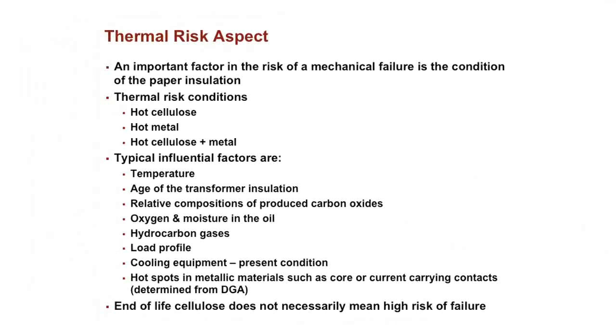Okay, so again, going back to what I was saying, you calculate the design, or what it was born with, so that's this part, and then the environment that it was in. So that's the number of through faults it saw through its life, and the size of those through faults, and then what is its condition now? So looking at the thermal and dielectric condition. All these things you use to calculate the overall risk of failure for the mechanical risk aspect. Okay, so now if we go to the thermal risk aspect, this is more or less the condition of the paper.